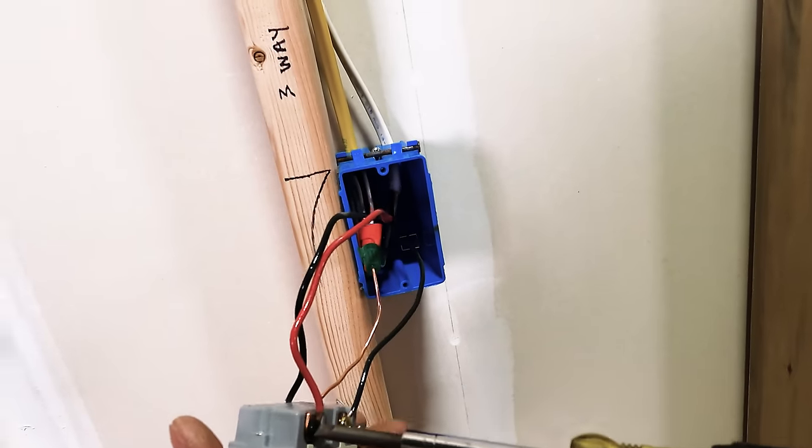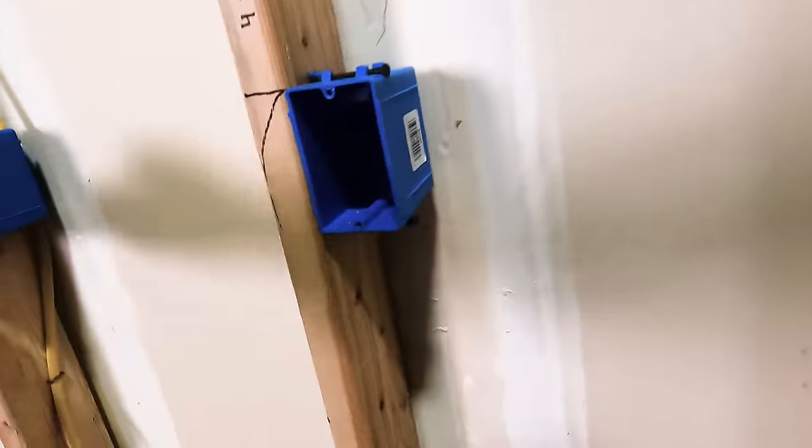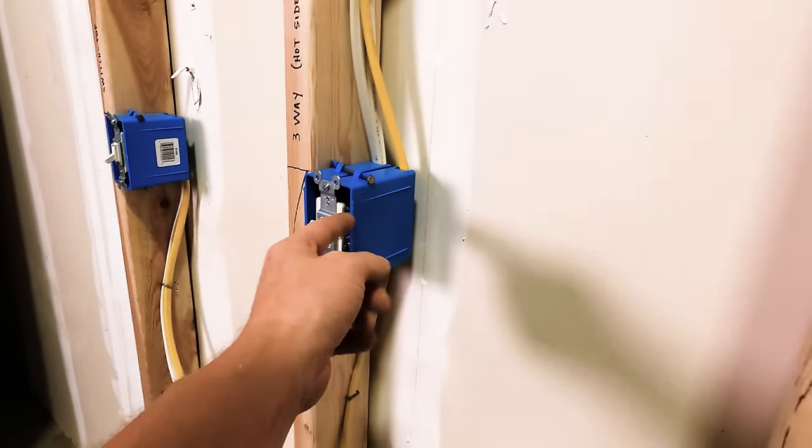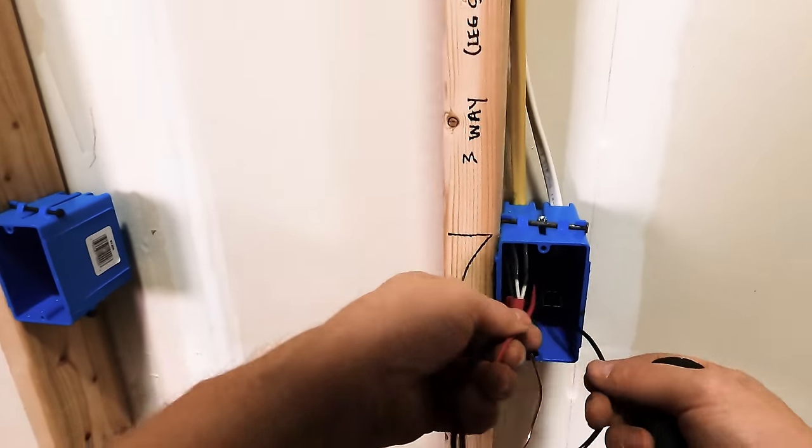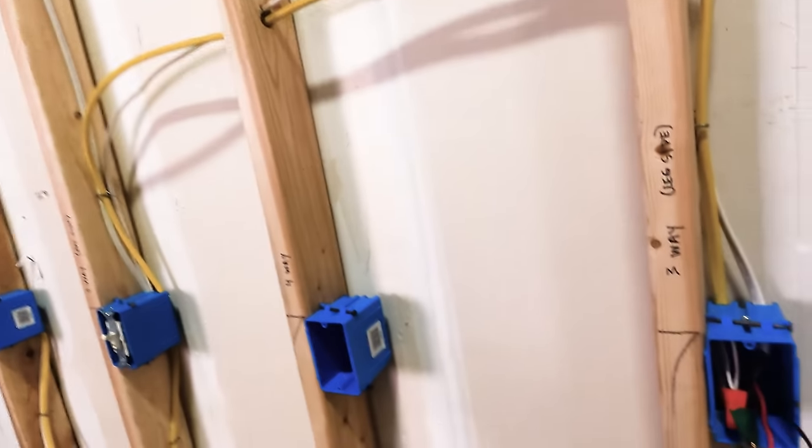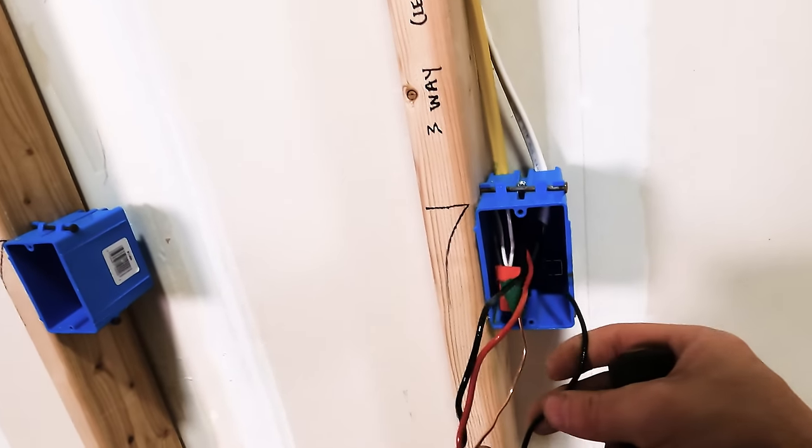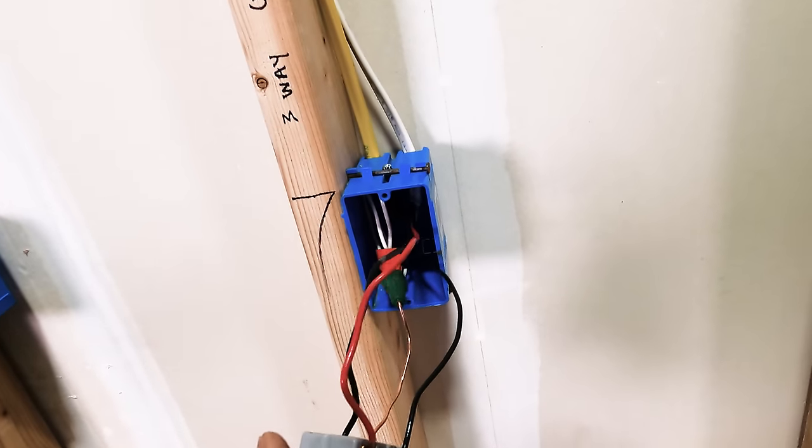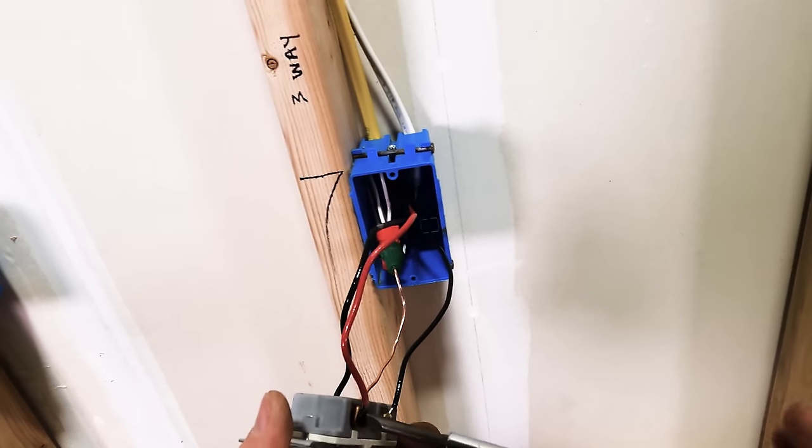Your switch leg and your hot on both sides of a three-way. This is your hot side. Your hot is always going to be on the black screw on this one. And your switch leg going up to the light is always going to be on your black side on this device. So let's just switch these two around.